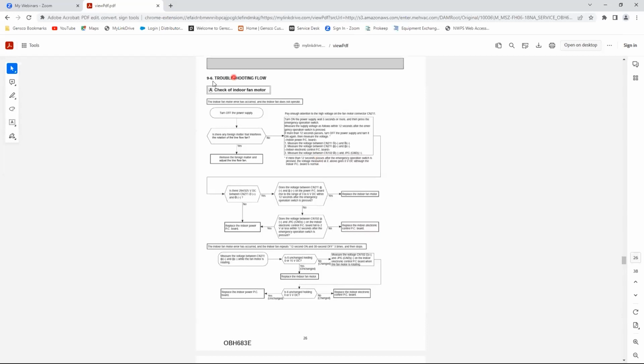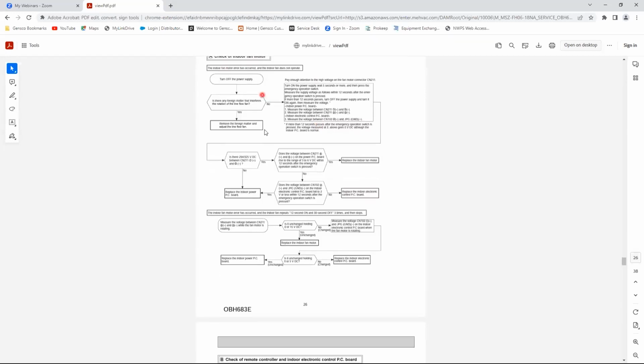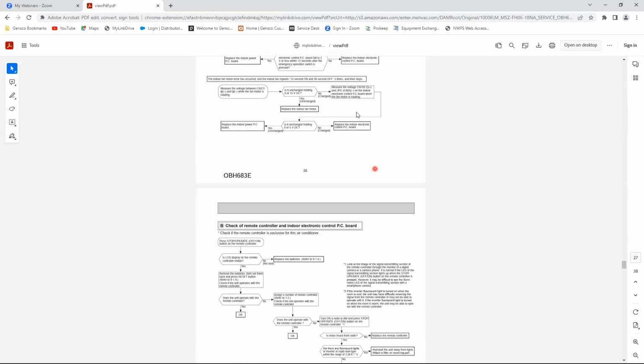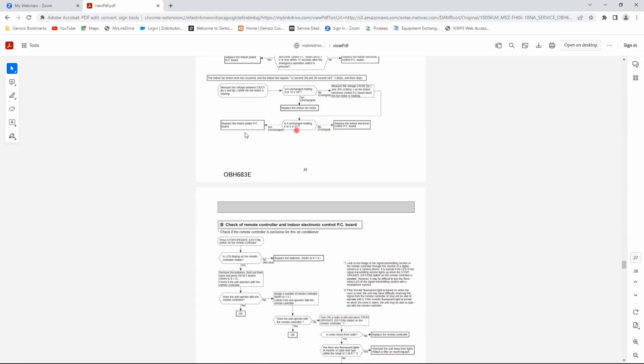Here we have a troubleshooting flow chart for our indoor fan motor. You follow this, answer yes or no, and it leads you through the troubleshooting path. So yes, you can troubleshoot your own unit if you know where to find this information. Hence, that's why we are having this class. Not that we don't like to talk to you, but if I can make you more self-sufficient and timely, you can do more jobs in a day. So you follow this, answer yes or no, and it will lead you to a solution. Replace the indoor power PC board or replace the indoor electronic control PC board.